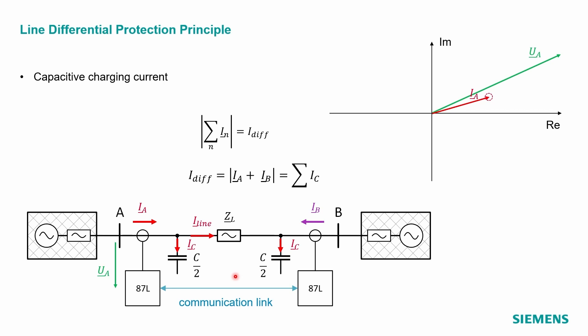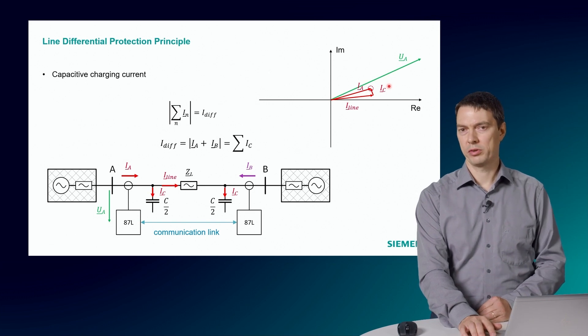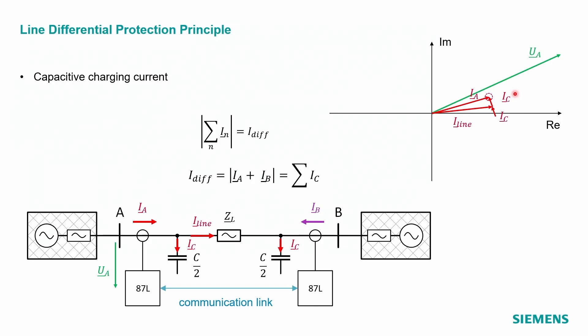Consider we have a load current situation with the current IA and the voltage UA at the terminal A, which are more or less in phase. That means that the cosinus phi, the power factor is close to 1. The capacitive current IC is added to the current IA and forms the line current. We ignore the voltage drop of the line impedance and can add at the terminal B another portion of the capacitive current IC and get to the current IB in the opposite direction. The sum of both current phases result in a differential current IDIF.